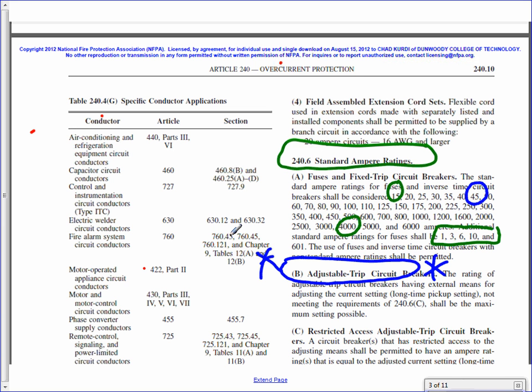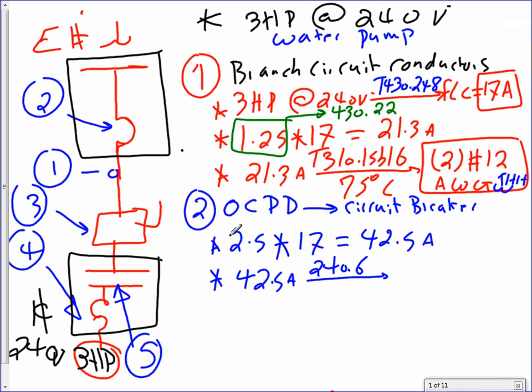If you look at 42.5, what's my next standard overcurrent device? I have 42.5. My next standard is what? 45. Can I have thumbs up, Chad? We know how to use this table. It's a crime against humanity if you leave Dunwoody not knowing how to use these tables. So everybody knows now I went to 45 amps. If it's not a standard, you go up to the next standard. Okay?